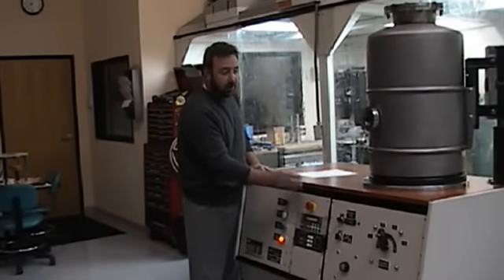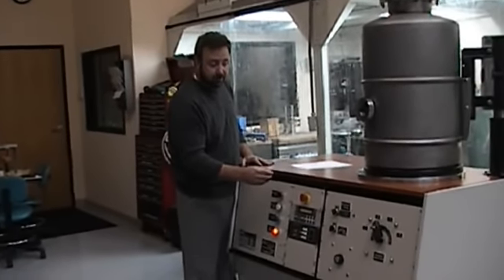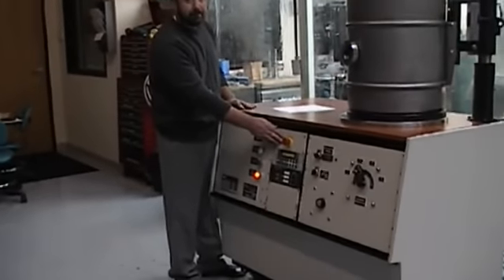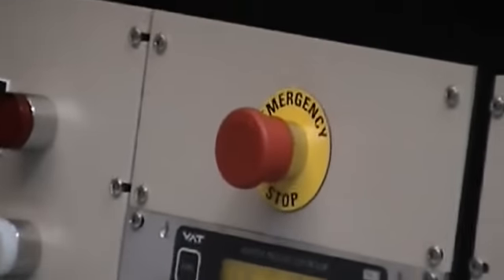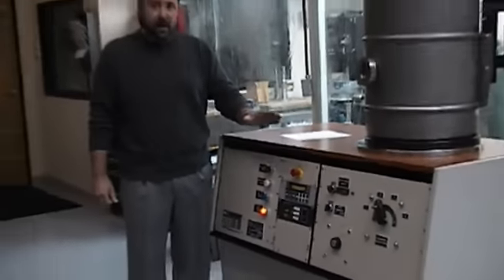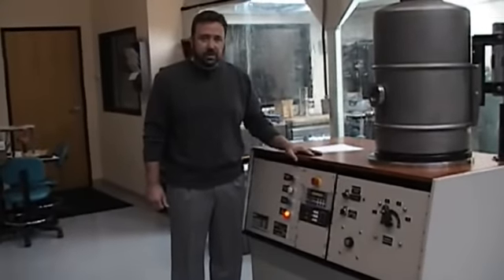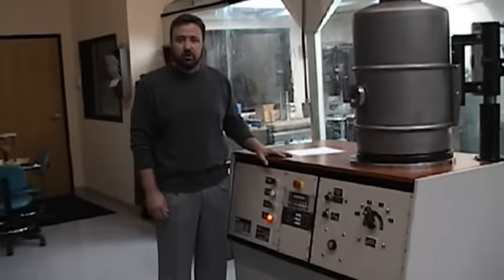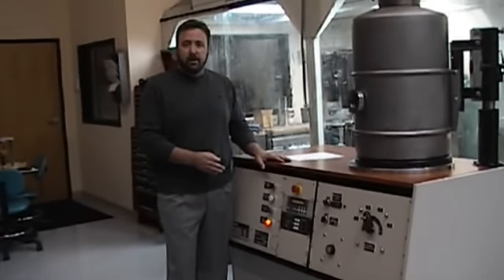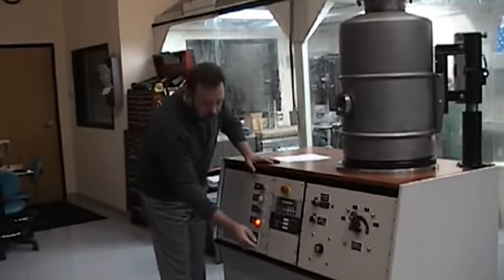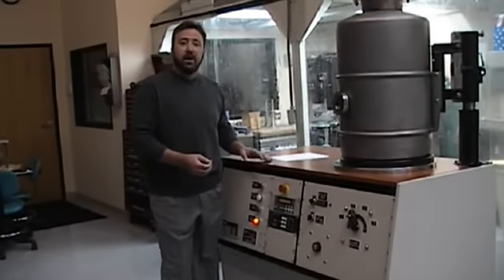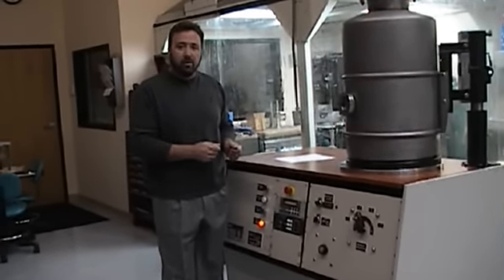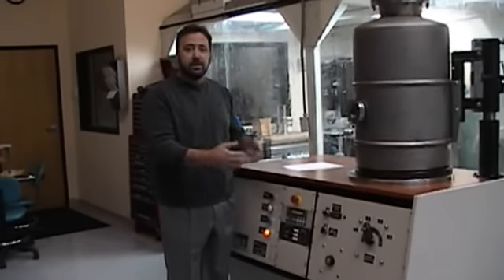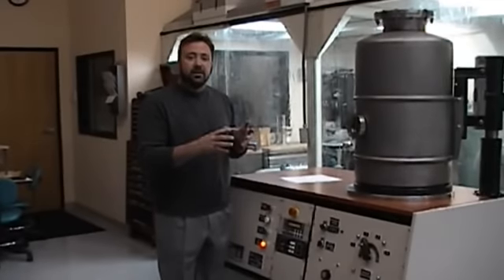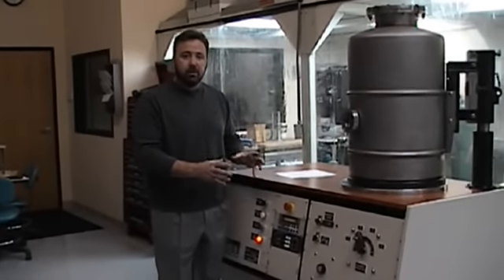One switch I did not describe while we're waiting for the bell jar to vent is the emergency stop that you see right here in red, labeled in yellow. Emergency stop is designed as a front panel disconnect basically for our controls. One thing should be noted, that the control transformer located down below here, which provides us 120 volt power, steps our 208 volts down to 120 volts, is constantly powered up.